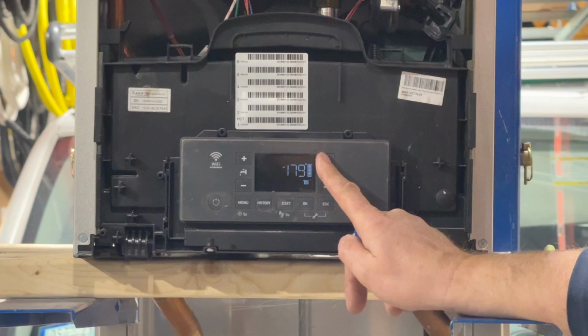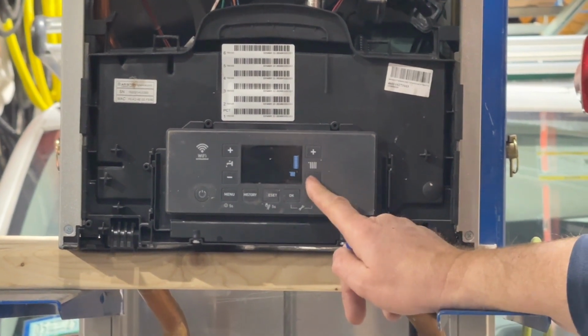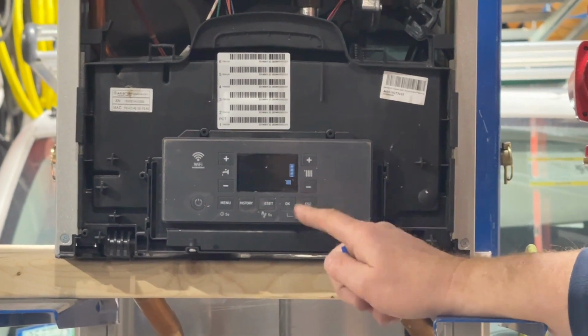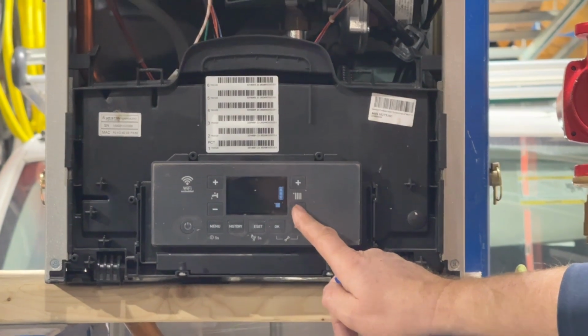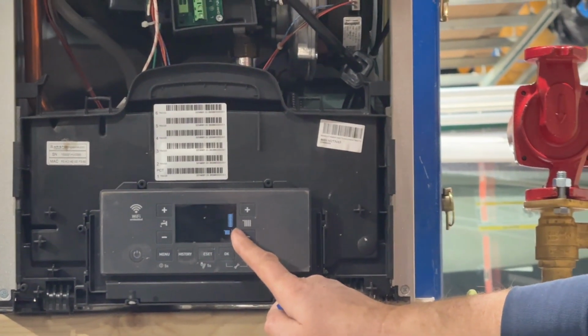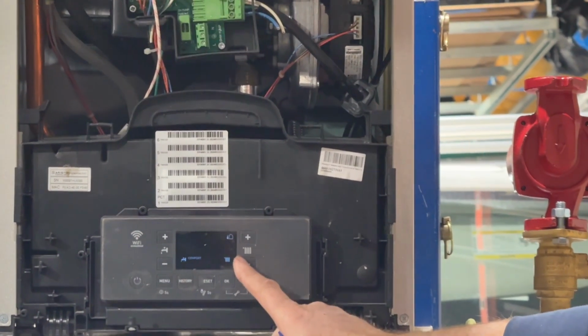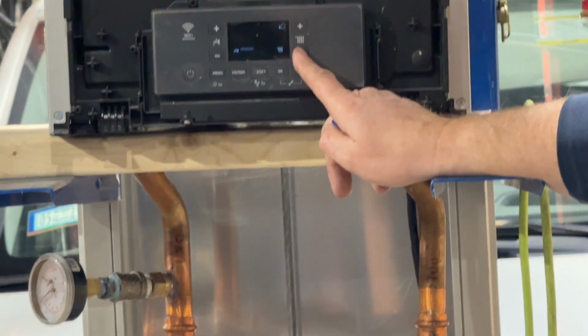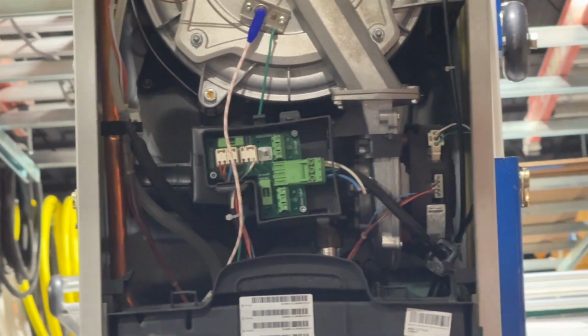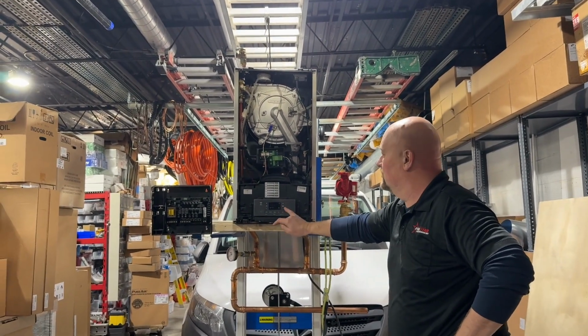Maximum is 180 or 179. That's for radiators. These high efficiency boilers are not any good for copper fin tube. They don't give you enough heat. You need 190 to 200 degrees for that. So you need a cast iron boiler for the radiators you installed in my cousin's house. This boiler cannot work there because the water would be too cold. You gotta have a cast iron old school boiler.